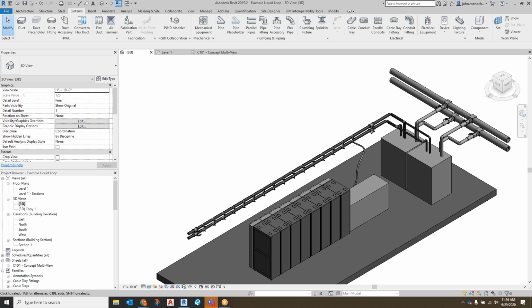And that's the key aspect of the reference design discussion: what do you want to provision, how do you want to provision, to make sure that when 4 years passes and you need to plug liquids into an older data center, can you do it just by pulling out the CRAH and plugging in a CDU? That may get you part of the way, but if you don't have a path left open for the pipe to go, it's not going to get you any further.